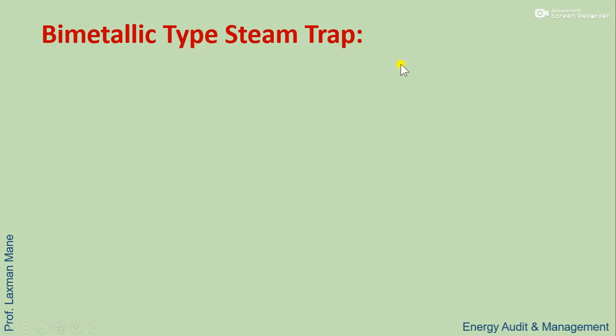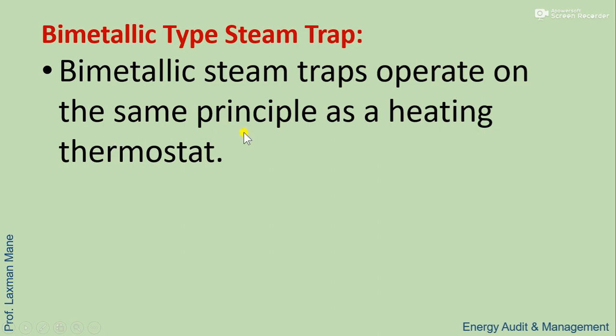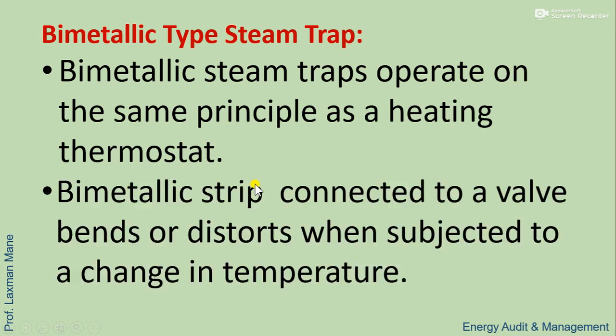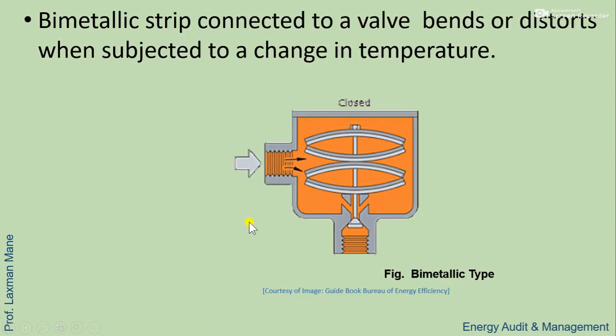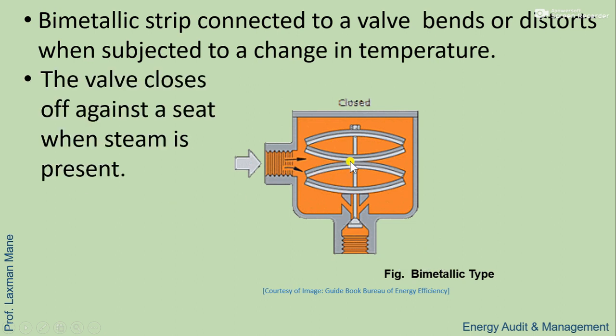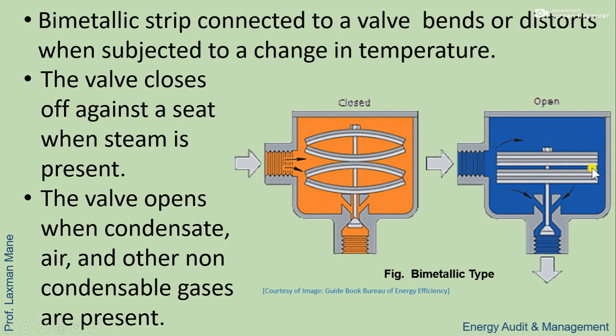Bimetallic type steam trap: the bimetallic steam trap operates on the same principle as a heating thermostat. It is connected to a valve that bends or distorts when subjected to a change in temperature. The valve closes against a seat when steam is present; the valve opens when condensate, air, or other non-condensable gases are present, releasing them from the system.